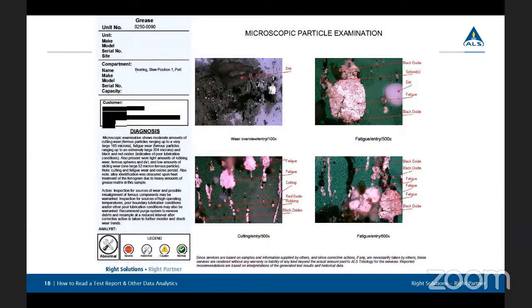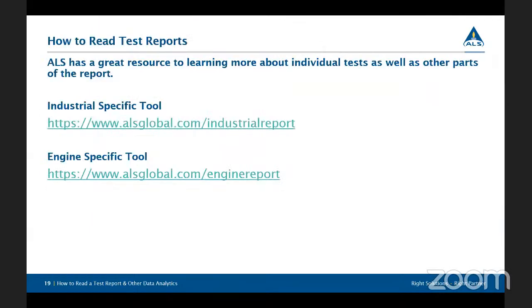So it's really good to make sure that you're testing both ends of the spectrum, to make sure that good clean product is going into your system, and that what you're getting in your oil analysis results is truly representative of what's being generated by the piece of equipment.